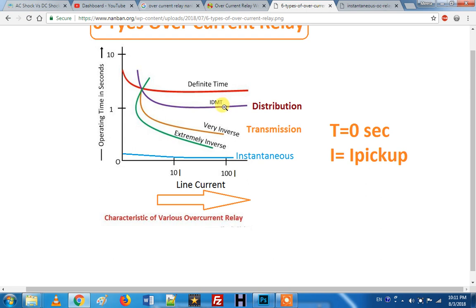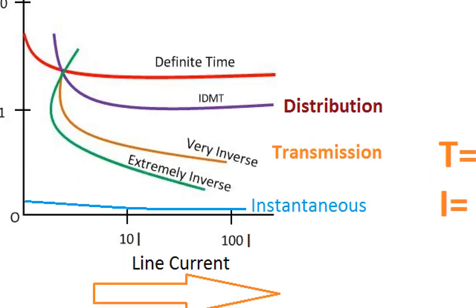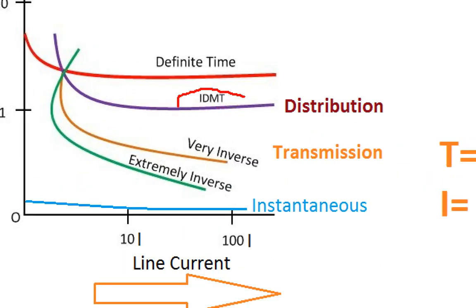If we say IDMT, what is the basic concept of inverse? The timing is inversely proportional to the current. For example, if it is 10 amps it will be 5 seconds; if it is 100 amps it will trip faster. So the relay has different characteristics depending on the current.